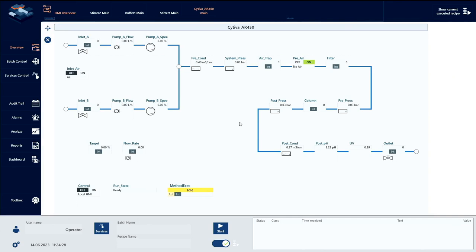The generation was finished and the project was updated in the zenon Engineering Studio. The only thing we do in the Engineering Studio is create the changed runtime files — only this. We load the changes and voilà — this is how you can quickly implement a device via MTP technology. We have everything connected to the system using the MTP gateway. Their system is still operated via the Unicorn software, but all signals are exposed to their OPC UA server, and in the middle our MTP gateway connects to Cytiva's OPC UA server, translating signals to the MTP world.